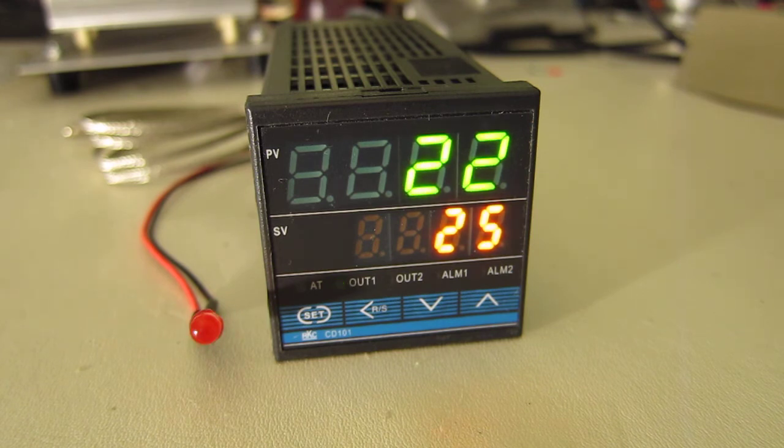So now the PID controller is running and you can see that it's indicating 22 degrees Celsius temperature, which is the room temperature with the thermocouple sitting here on the bench. I've got the set point set to 25 degrees Celsius which is just above the ambient temperature and you can see that the output one light is flashing.